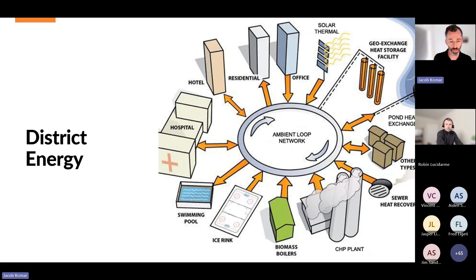So for example, let's say you have an ice rink in your community. The typical ice rink rejects about 1.2 million kilowatt hours of heat per year. You pay to freeze the ice, and then you pay to reject the heat from freezing the ice. But that heat can be used in buildings. That 1.2 million kilowatt hours, if we take a typical duplex heating demand, I can heat 90 homes.